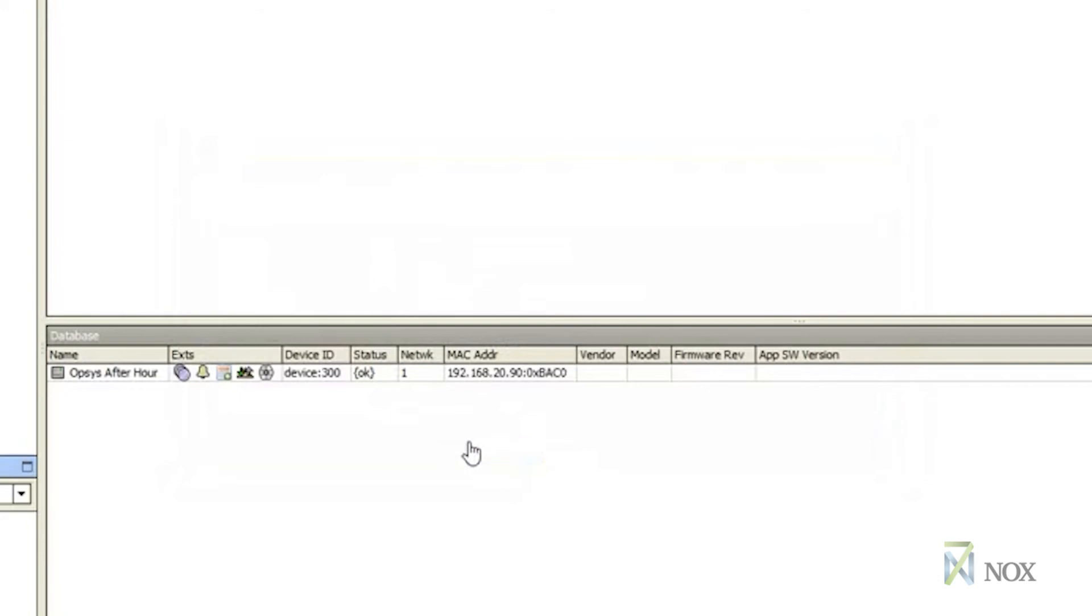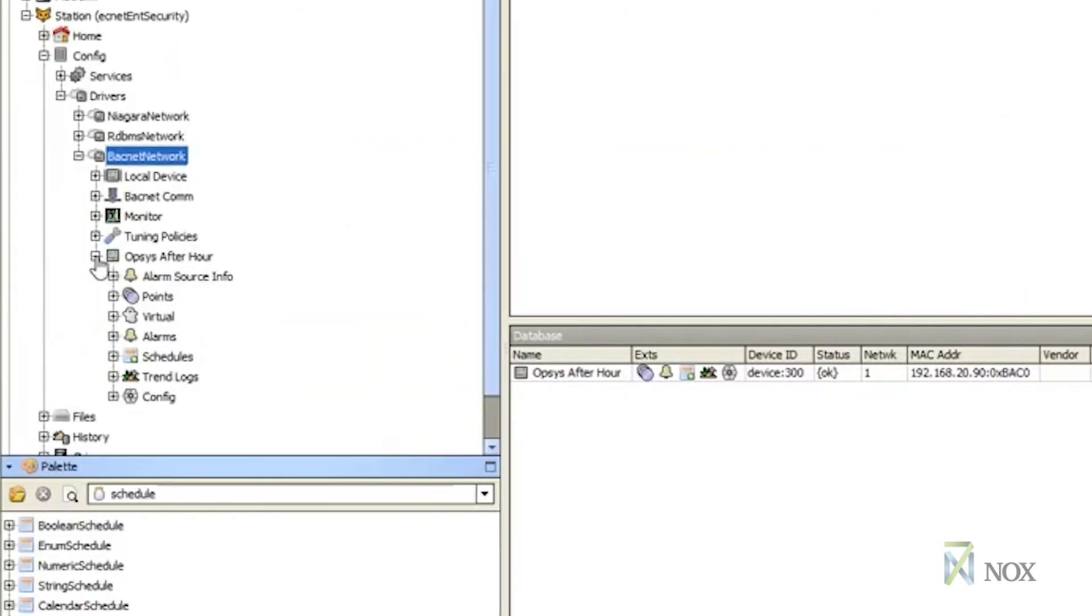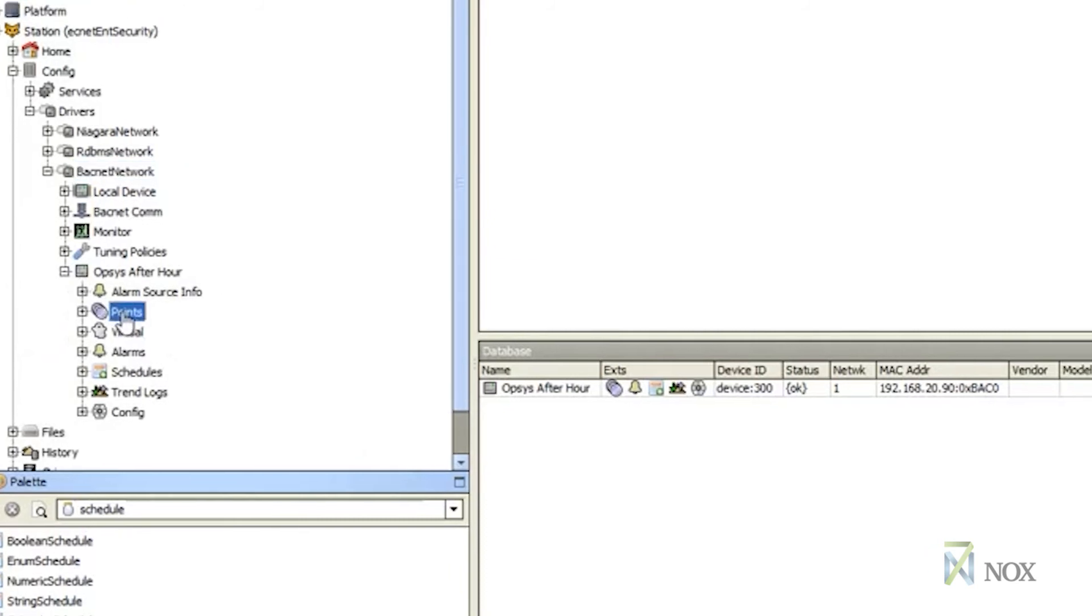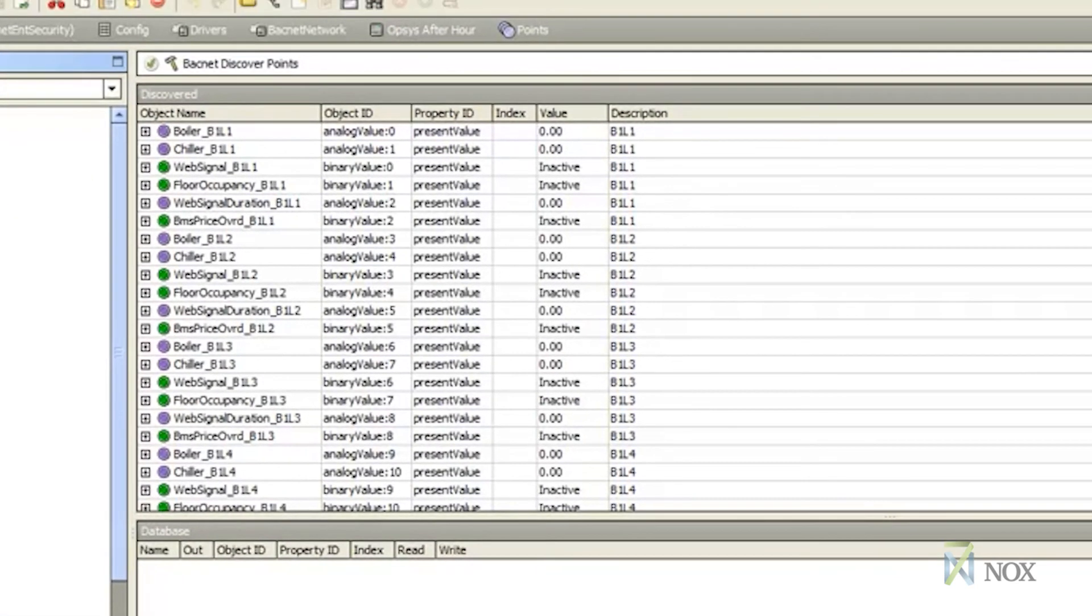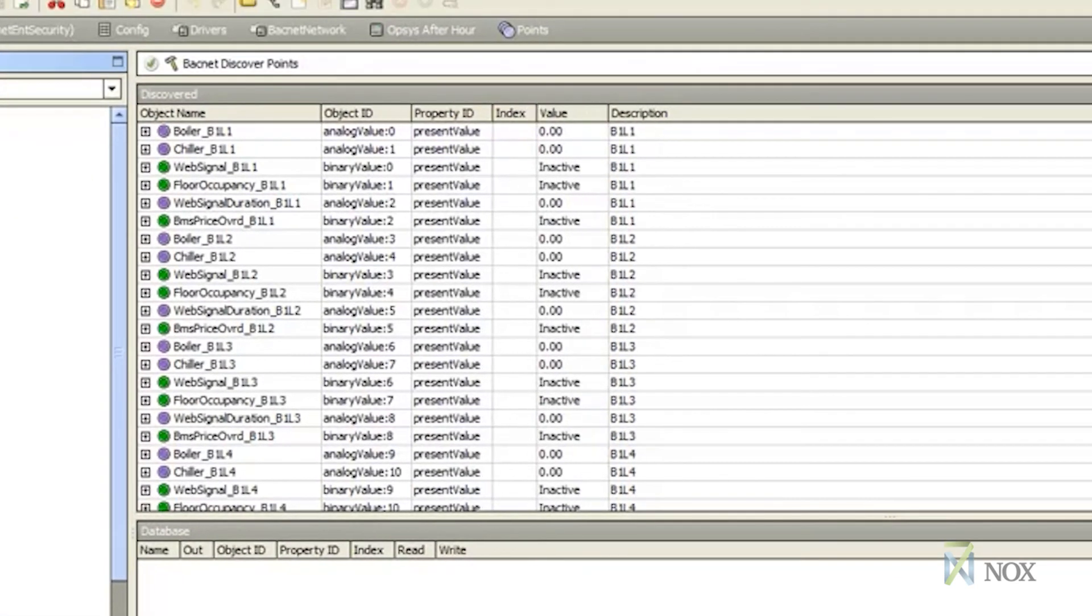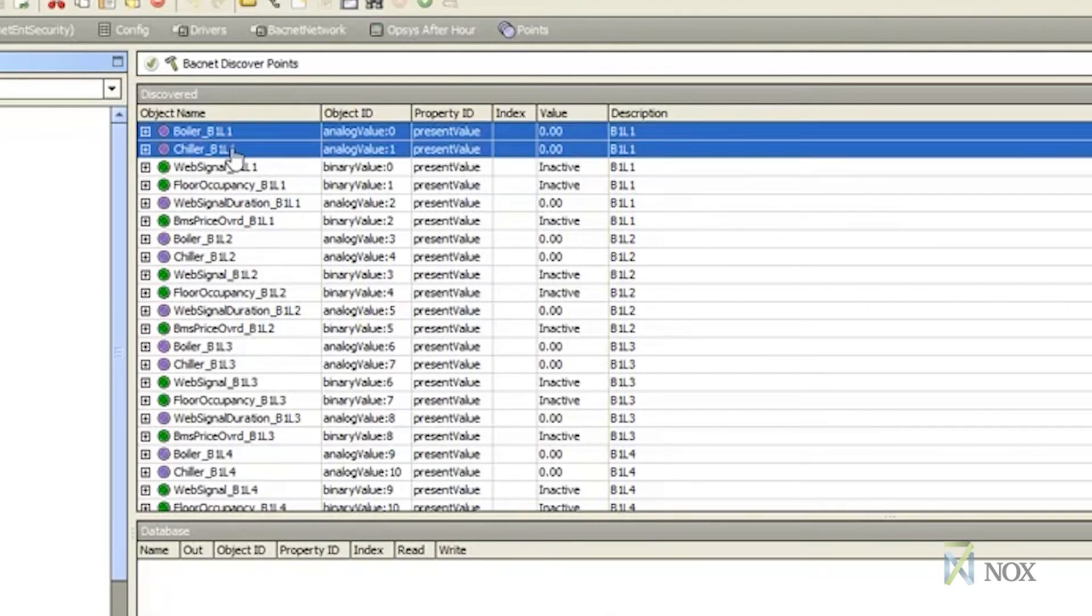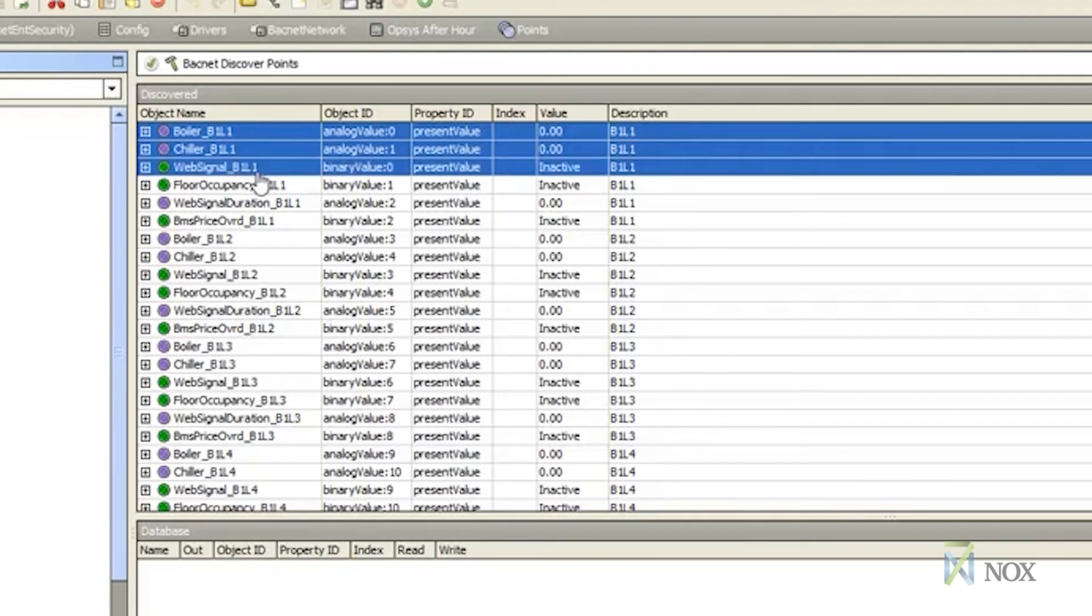Once the device has been added, it will appear under the navigation window. Under Device, click on Point and hit Discover. Once the points have been discovered, you will see them appear in the window under the BACnet Discovered Points. There are four different kinds of points configured in the NOX device.